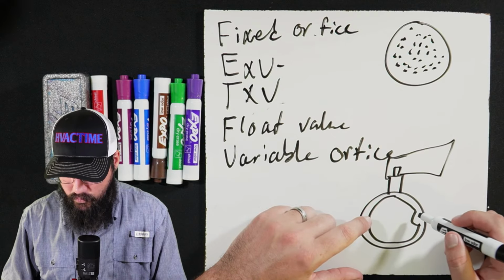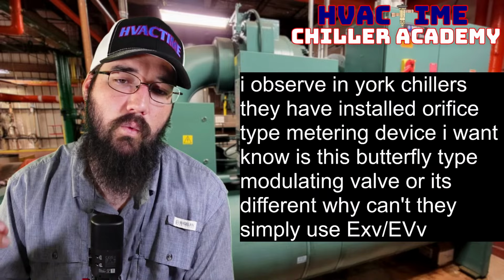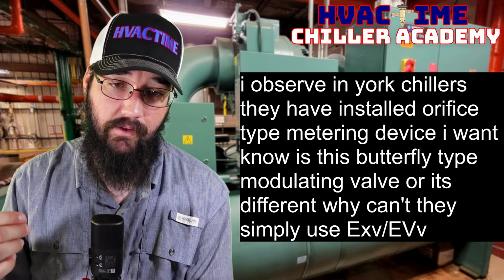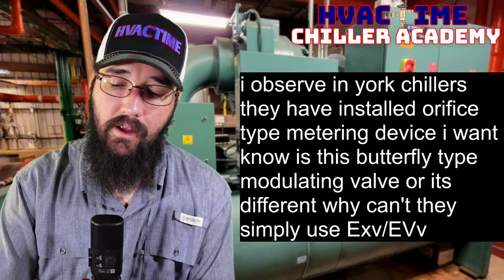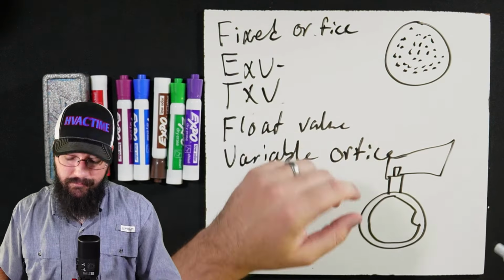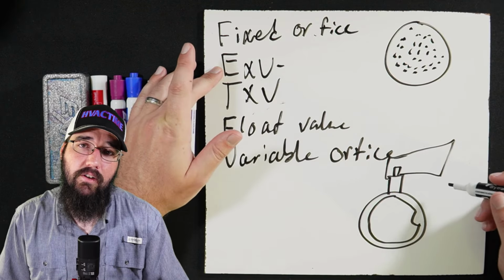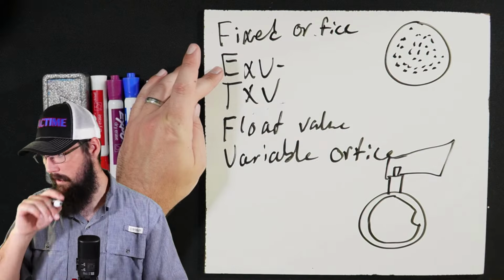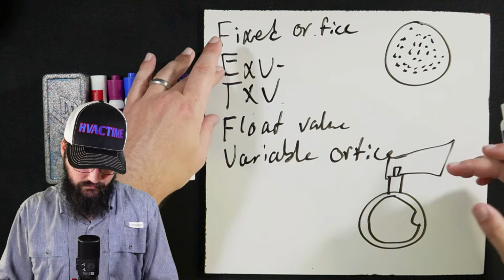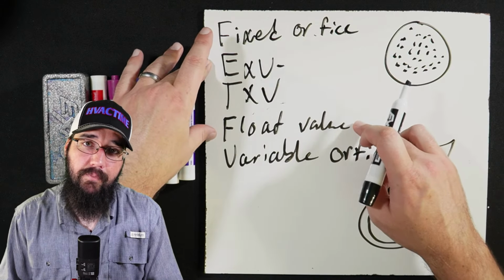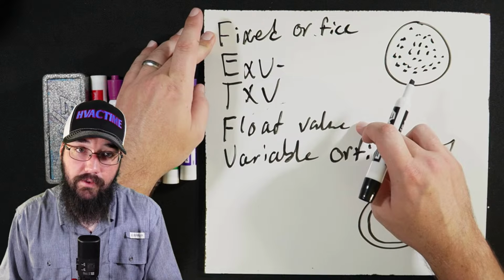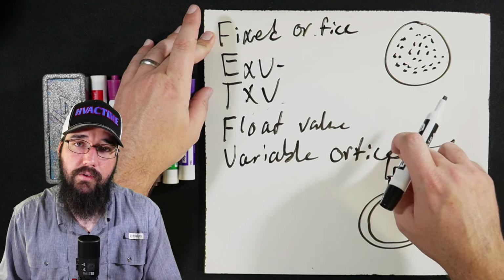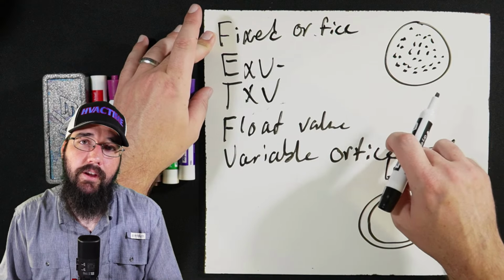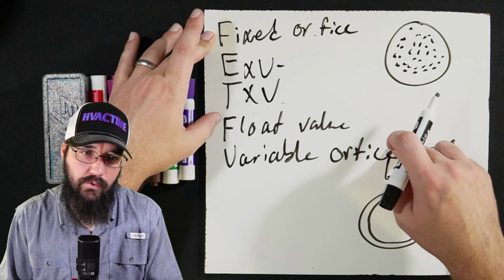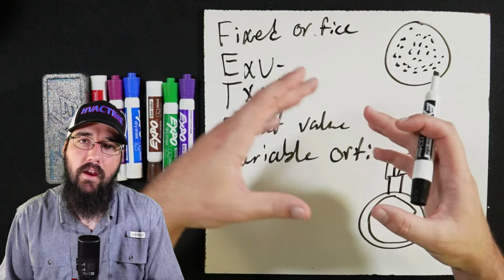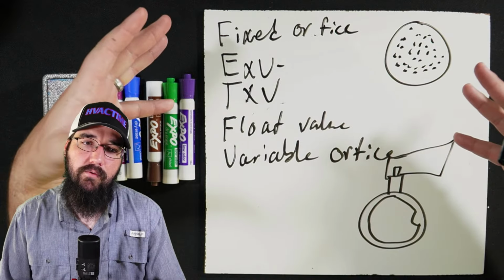Now, the second part of that question is, why not use an EXV instead of a variable orifice? That comes back to scalability. EXVs can only scale to so big before they just become completely impractical. That's why these float valves work so well. That's why fixed orifices work so well. That's why a variable orifice works so well. And that's why these machines that can really scale in size a lot use these types of valves, because EXVs only get so big before they just become impractical.